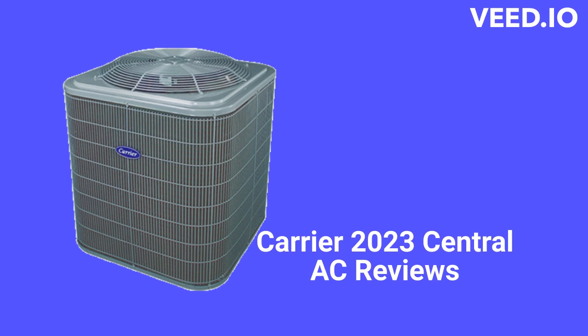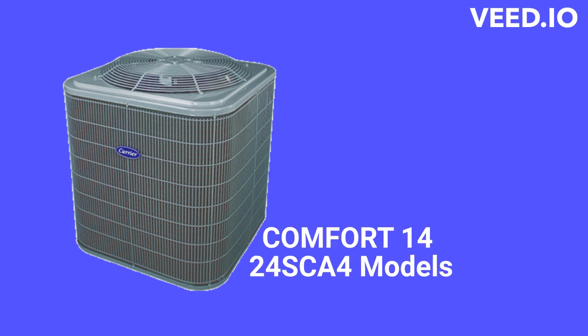This brand is made in Mexico and is available in the USA and Canada through their authorized dealer network. The Comfort 14 24SCA4 air conditioners are basic units with a 14 SEER efficiency. They have a durable powder coat finish but only a wire coil guard, which is not very effective at protecting the fins of the condensing unit from mechanical damage. They have scroll compressors and factory-installed filter dryers for system durability, but the units are relatively loud during operation.